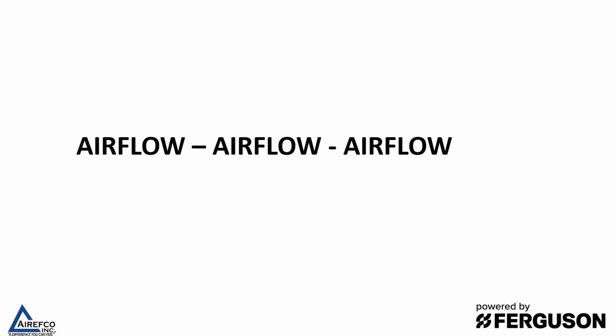But if you're having problems with a furnace tripping on limit switch or any heating problems, you're going to have to follow some of the examples that we presented in this video. So before you run your ductwork or before you condemn the furnace, take a look at what's connected to the furnace and how the airflow is in and out of the furnace. It will make a big difference on the proper operation of that furnace.